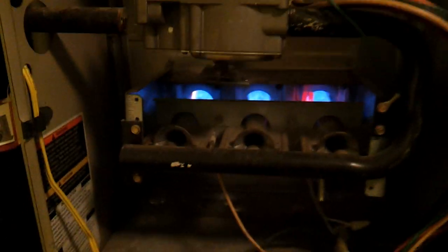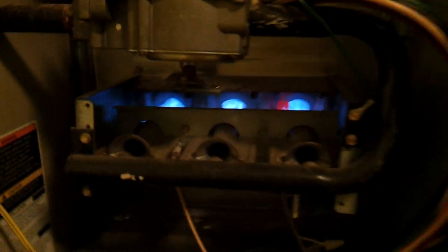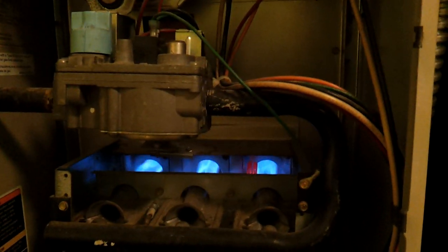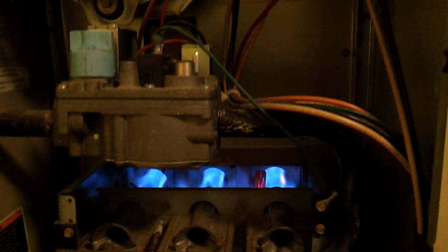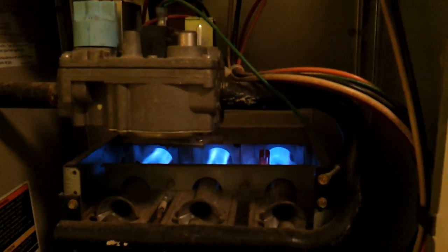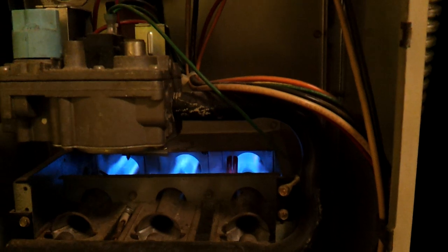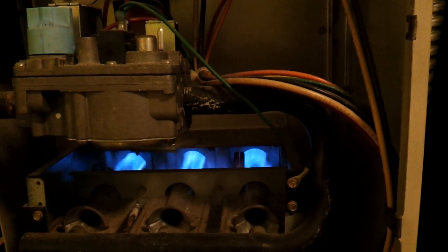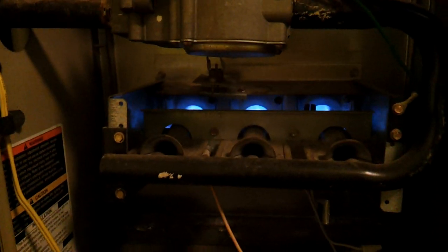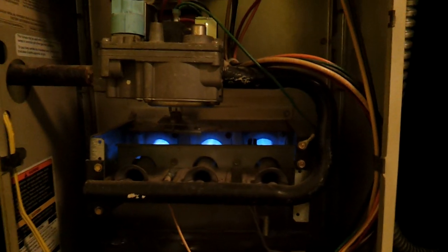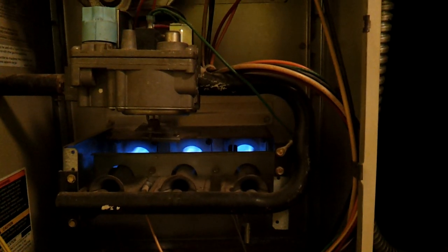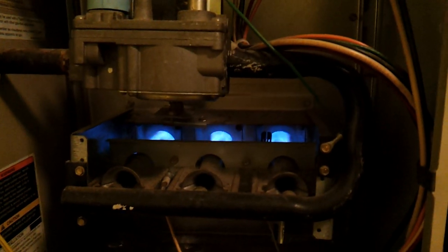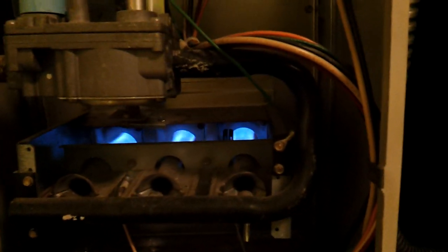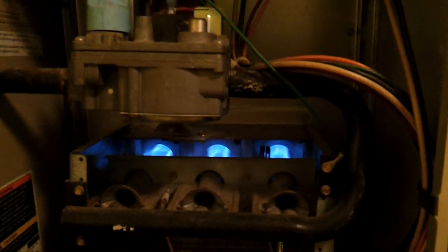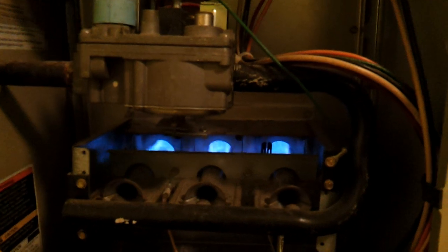And also back in there's a little thing called a flame sensor, which detects and makes sure that the flames are actually there. So if it doesn't sense the flames, it'll shut off gas flow to the unit. There's also in there what they call a flame rollout switch. So if the flames actually start shooting back out of the heat exchanger tubes, it'll shut down the unit. And that you have to manually reset yourself, because that could be a potentially very hazardous condition.